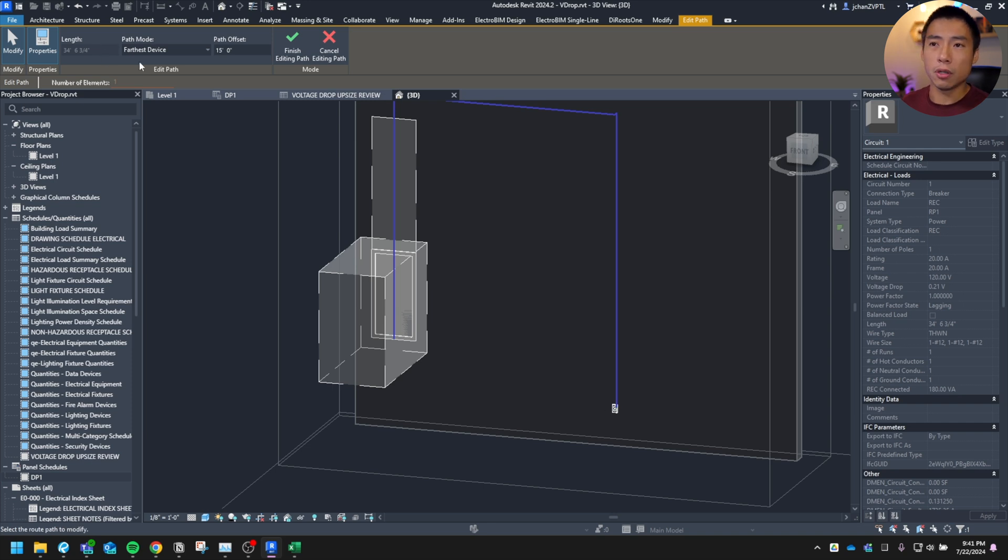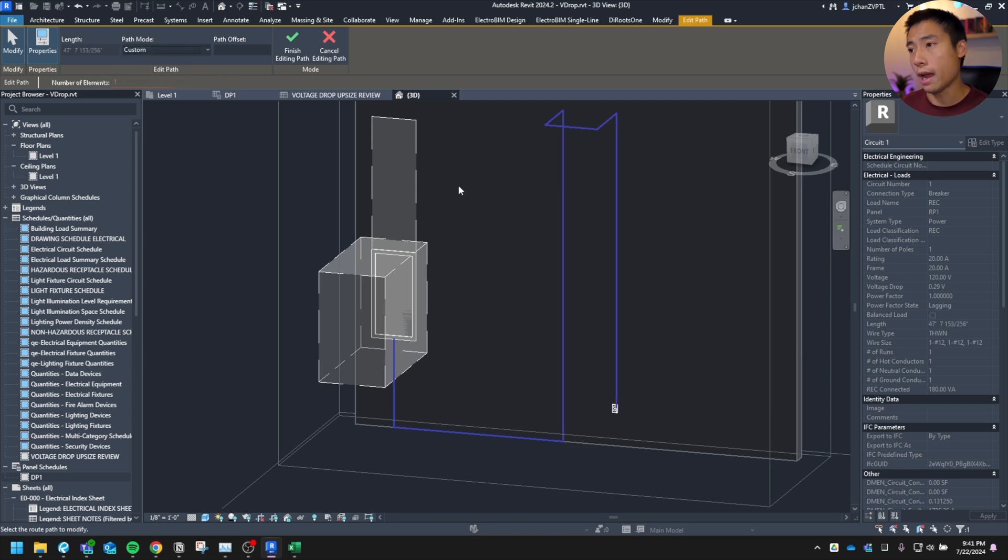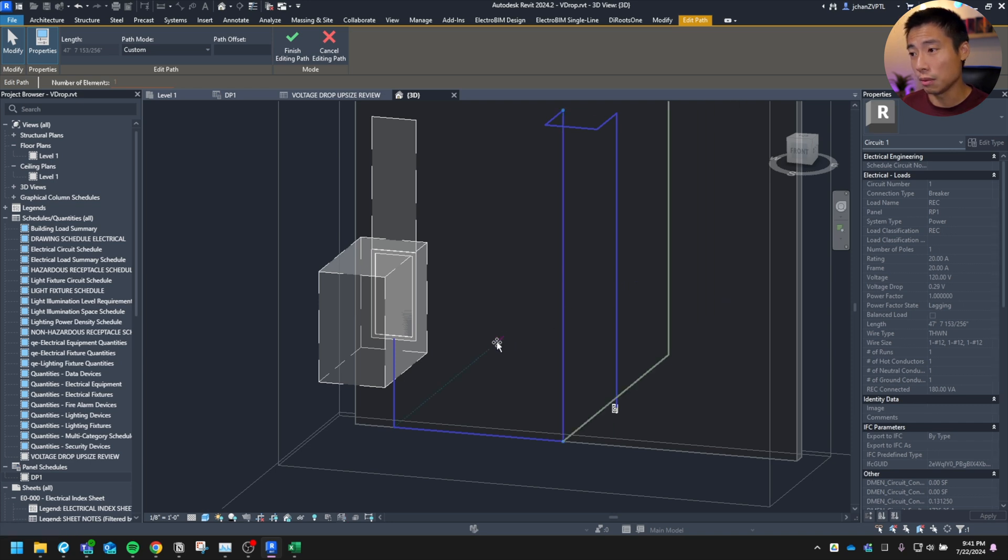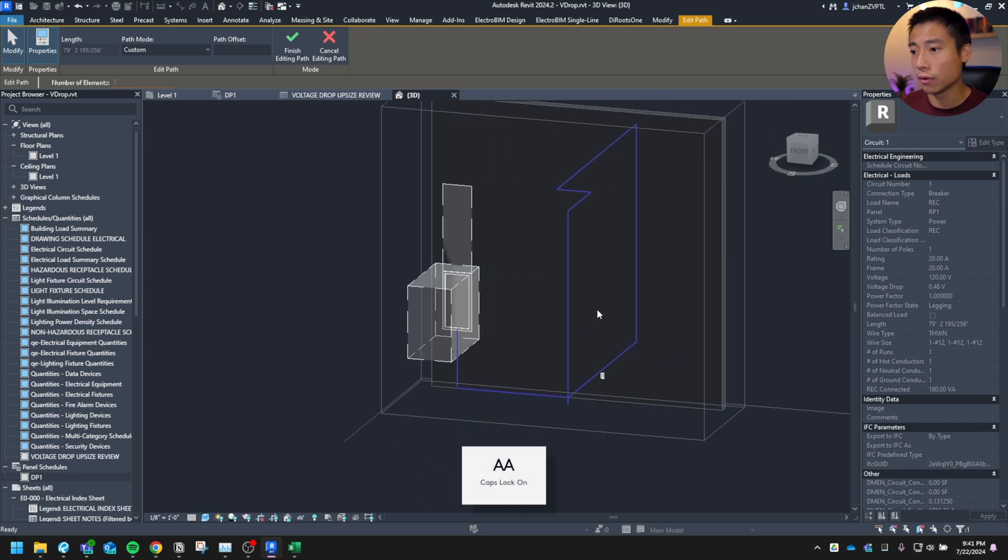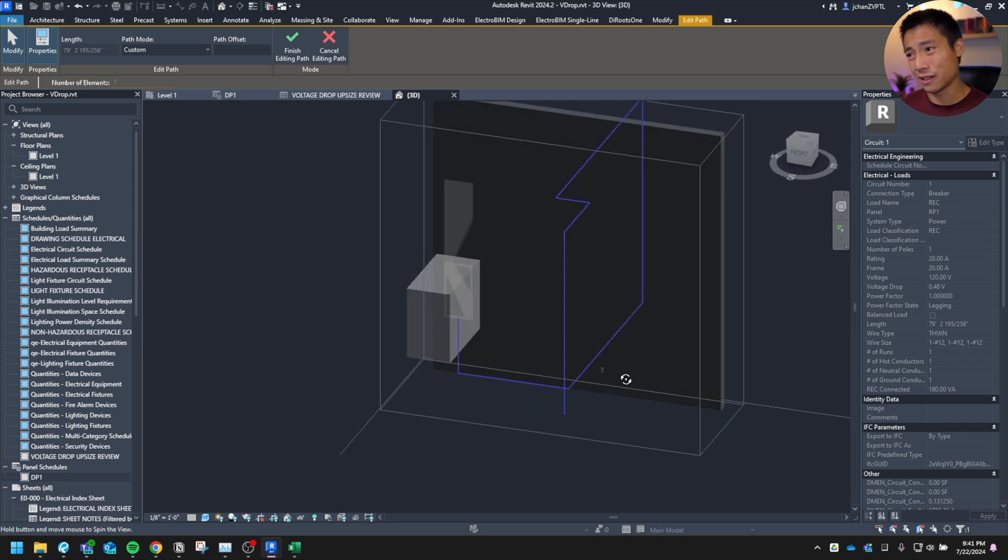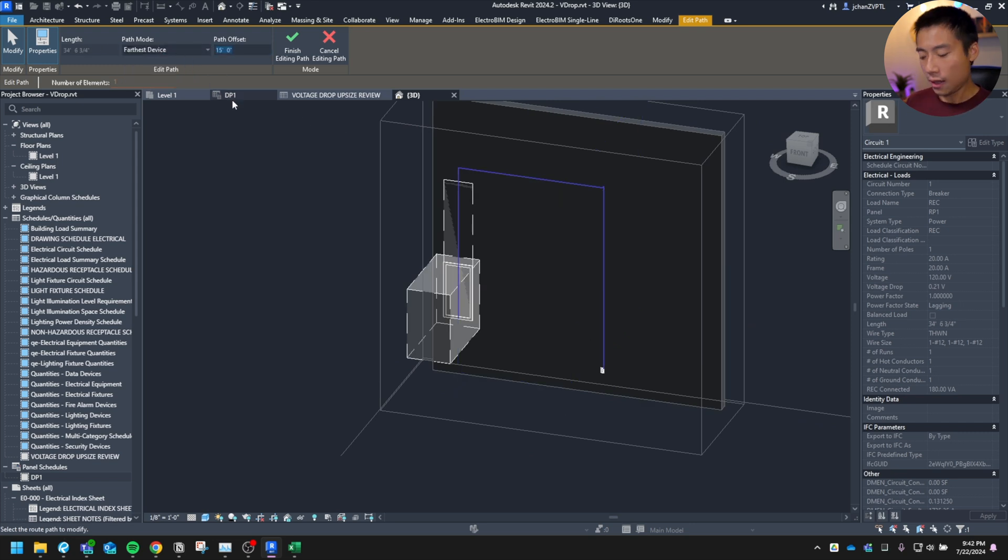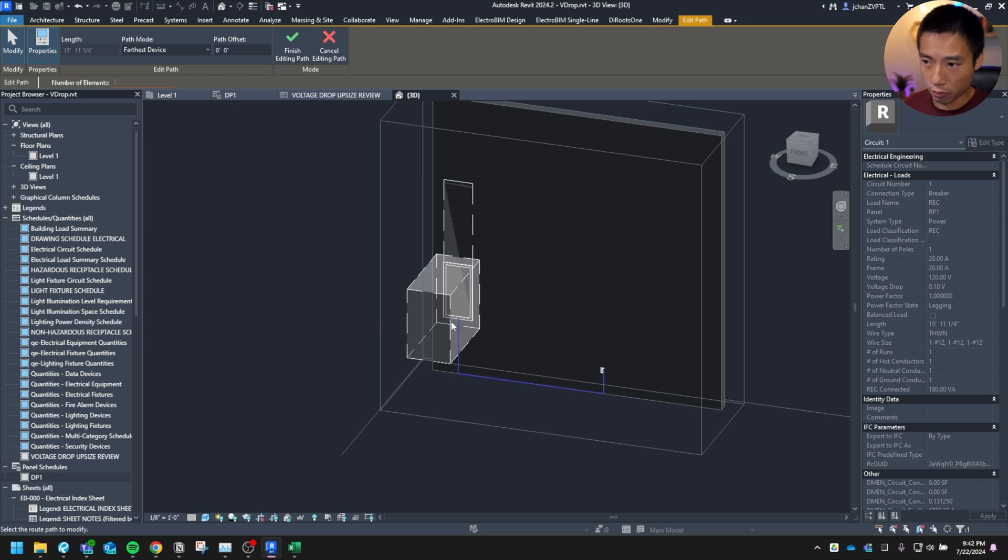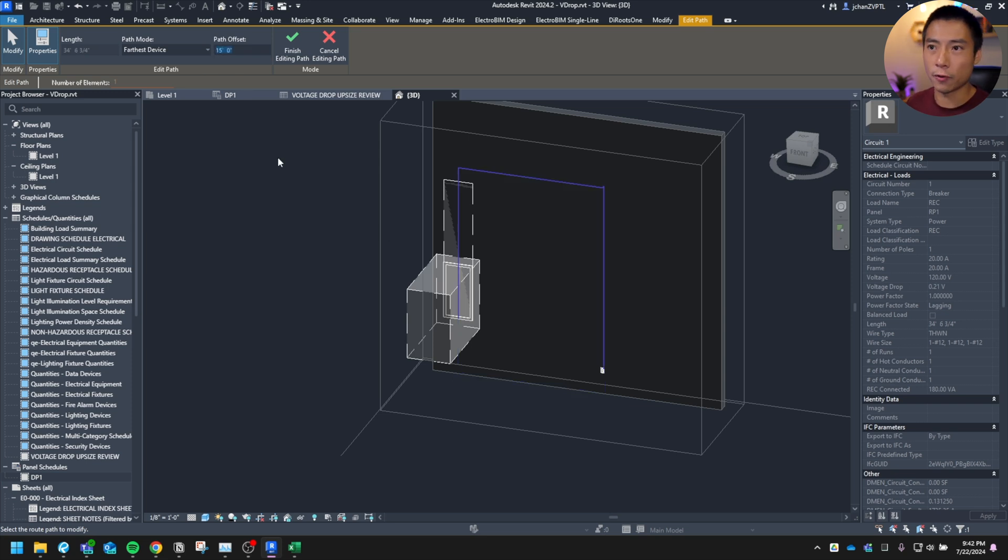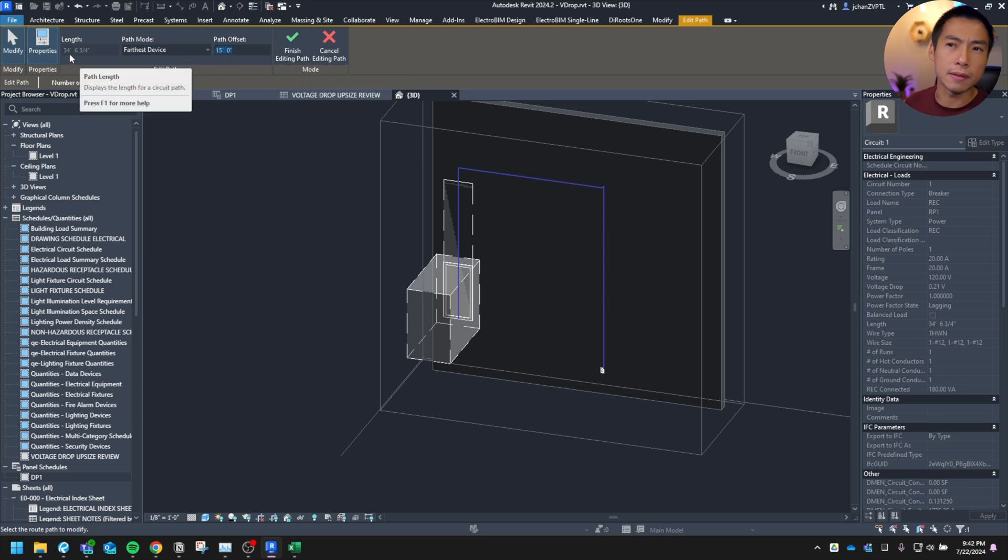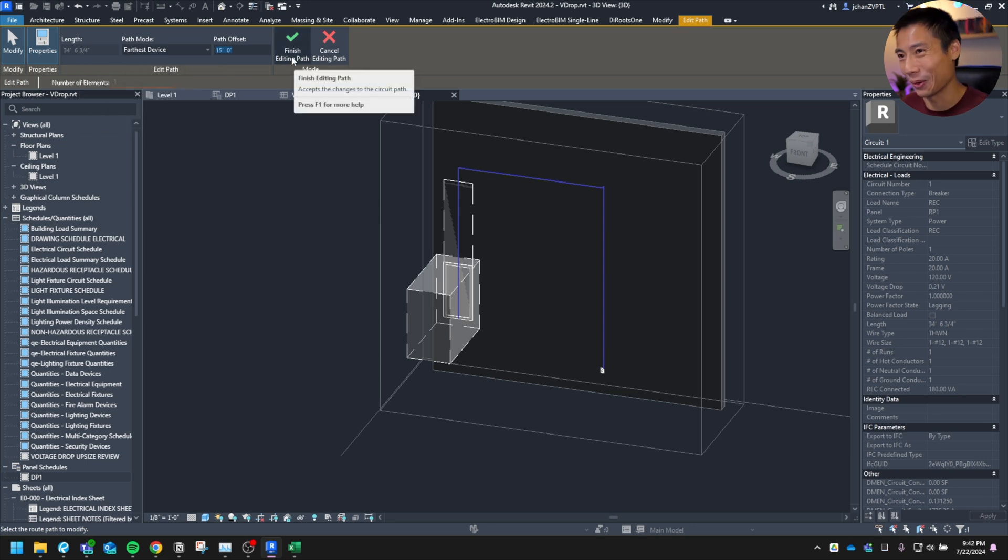So it goes up over and down. You can tweak this if you want it to. So like, if you hit all devices, I think it goes down. You can go all out and do custom and intentionally pull all this circuit, whichever way that might actually travel. You can see, you can get pretty crazy with it, but I don't do any of that. I just leave it at furthest device. And then if you like, you can put this at zero if the circuit's going to go down and over. But I generally assume up and over. So I leave it at that furthest device, 15 foot offset. Perfect. And it'll see a total length of 34 feet, six inch and three quarter. It's very precise apparently.